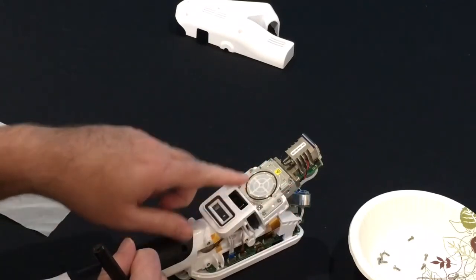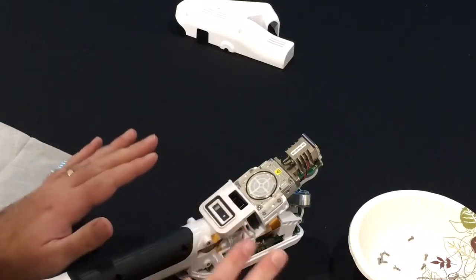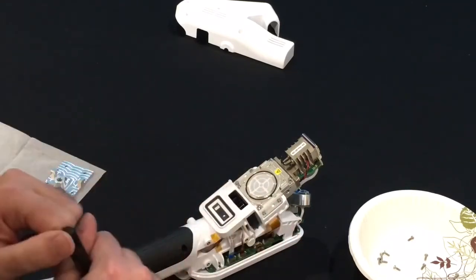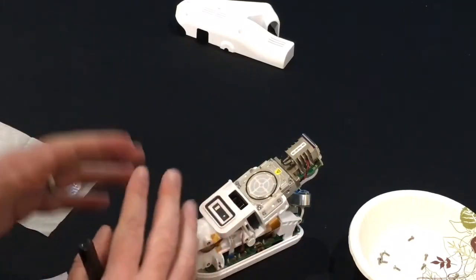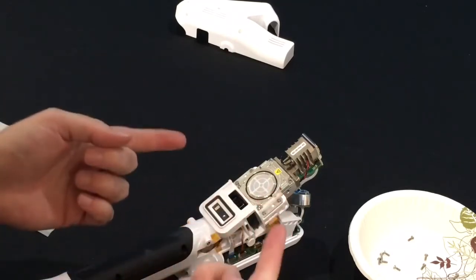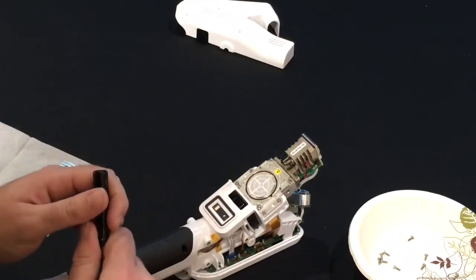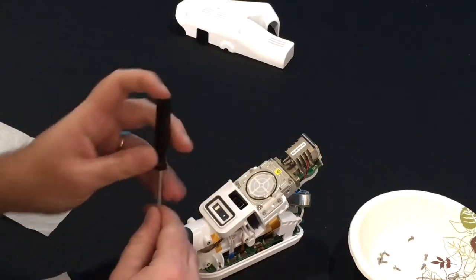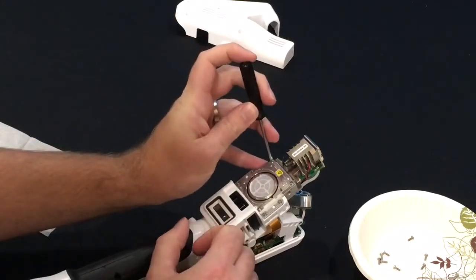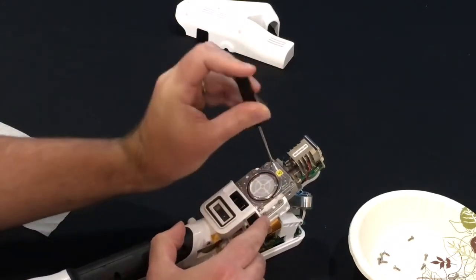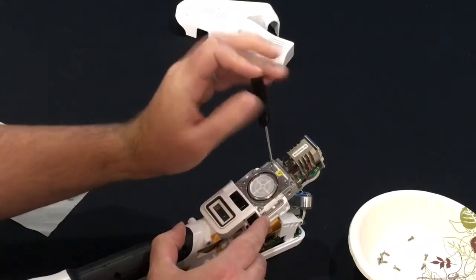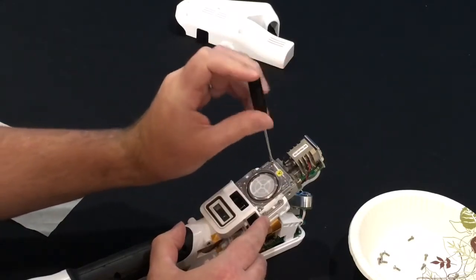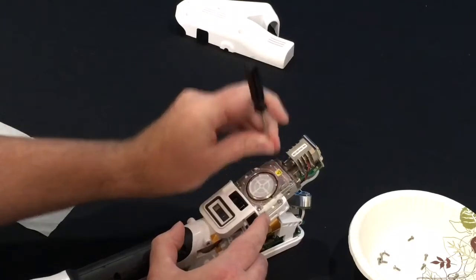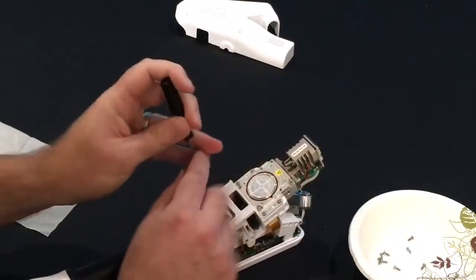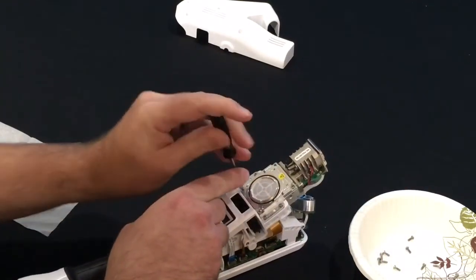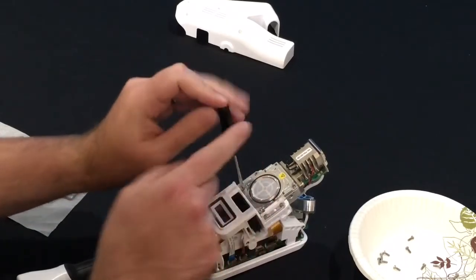You don't need to actually touch this filter, but if you did want to remove it separately from the pump cover, I would recommend using gloves so that the oil from your fingers does not get on the filter and cause problems later on. So, one thing we can do is just remove these 4 Phillips screws from the pump cover, and the filter will come off with it. Again, these are the same size screws, so you don't have to worry about keeping track of which one is which.